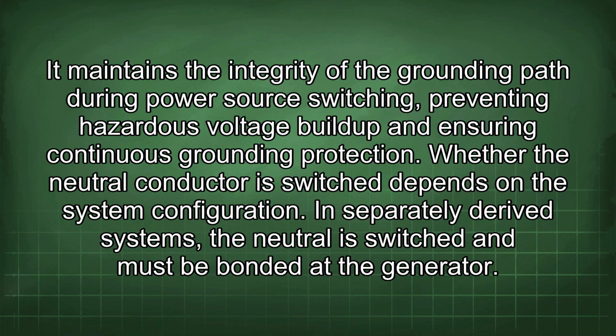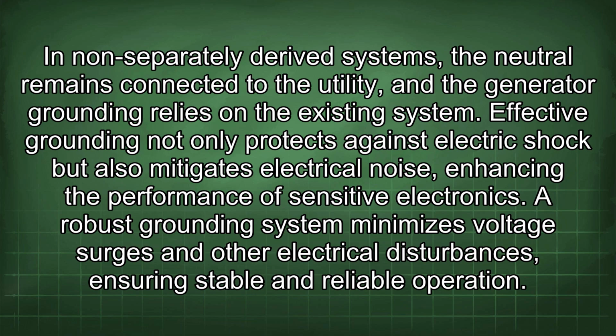Whether the neutral conductor is switched depends on the system configuration. In separately derived systems, the neutral is switched and must be bonded at the generator. In non-separately derived systems, the neutral remains connected to the utility, and the generator grounding relies on the existing system.